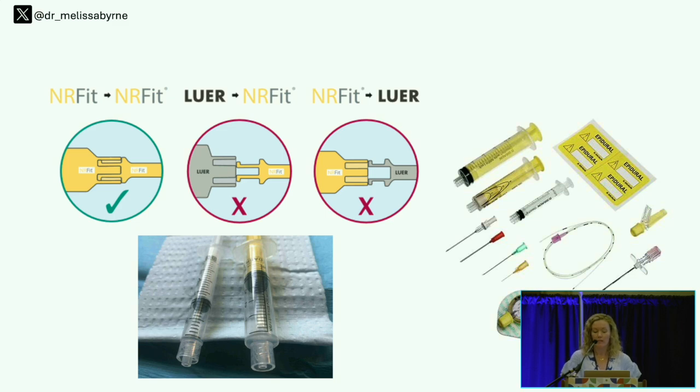In 2016, an ISO-compliant neuraxial connector that you see here was introduced. What's clearly visible is that the color is different, it's yellow, but what you may not also notice is that the diameter of the connector is smaller. Therefore, it should be less likely that you could take a medication intended for intrathecal or epidural administration and put it either IV or vice versa.